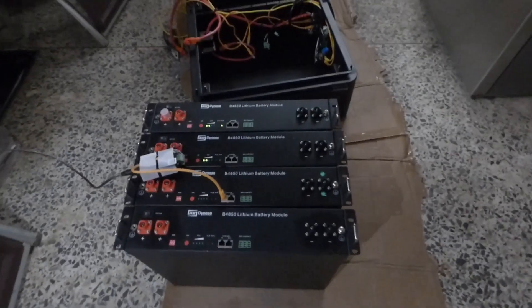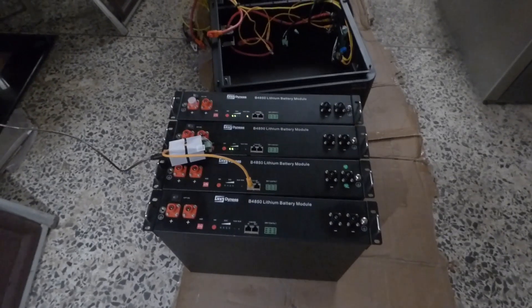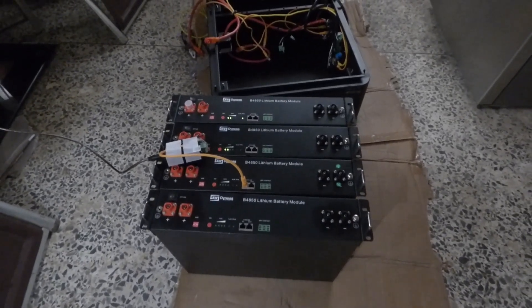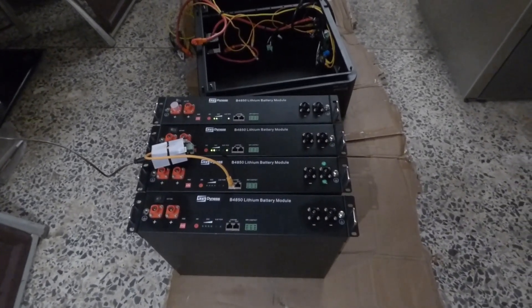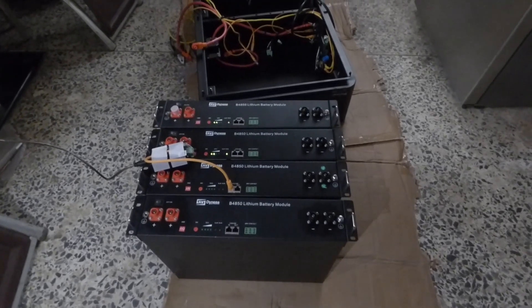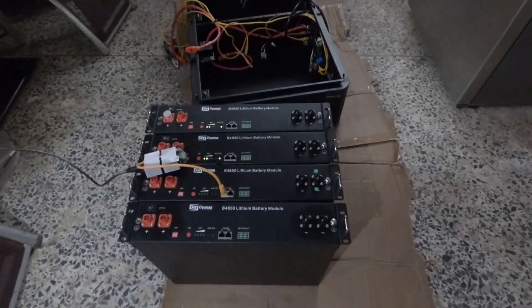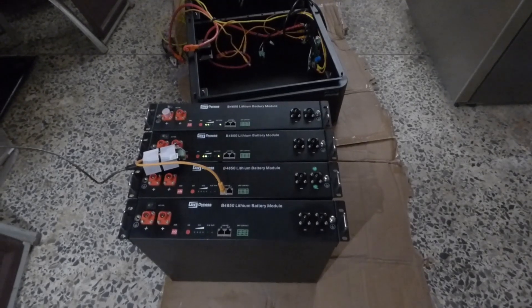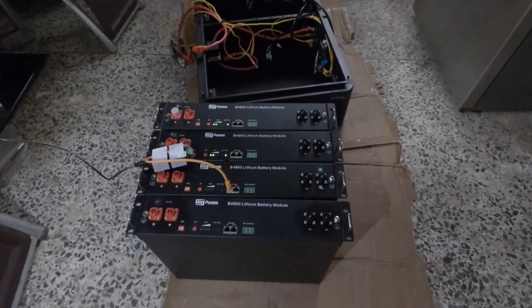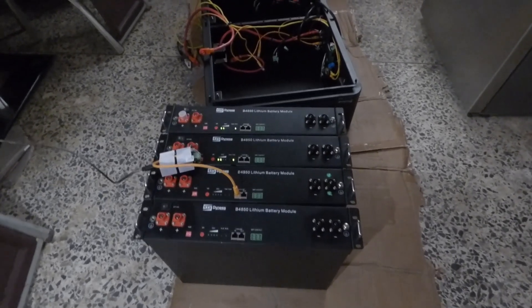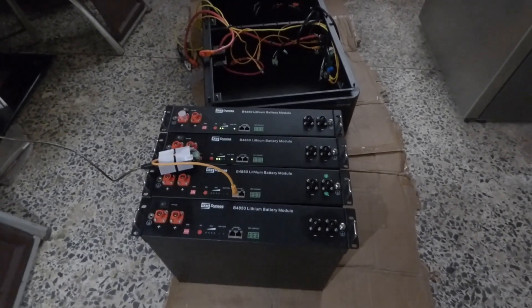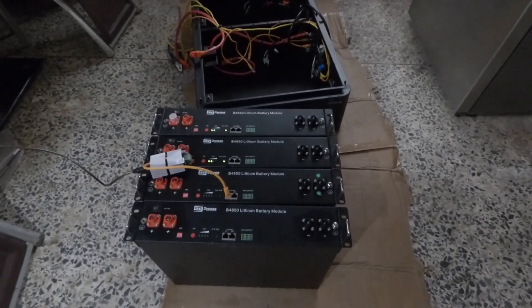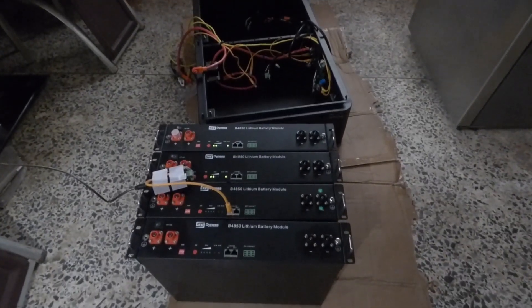That's not all. When it discharges as well, it discharges at a much lower amp. That one battery doesn't discharge as fast as the others. So it's created a problem for us where we have big capacity. We have 100% on one module and then we don't quite have it on the others. And as it discharges, you see one that's at 70%, while the others are at 40 or 50%. And then it tells you your state of charge is 50%.